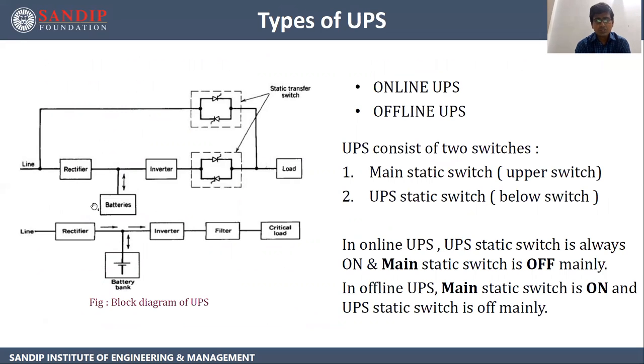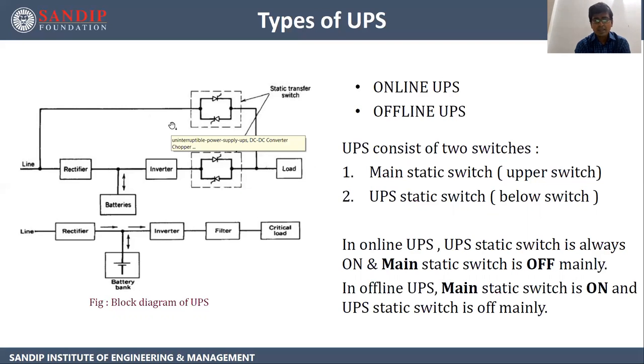That DC is going to be stored in these batteries. Simultaneously, this DC is directly fed to the inverter or through this battery, and this inverter will convert the DC into AC. Now there are two switches — one is the main static switch which is the upper one, and the UPS static switch which is the lower one. If the lower switch is on, this AC produced by the inverter is fed to the load. If the UPS static switch is on, then the main static switch will be off. In case the UPS static switch is off, then the main static switch will be on, and directly the line supply is fed to the load.